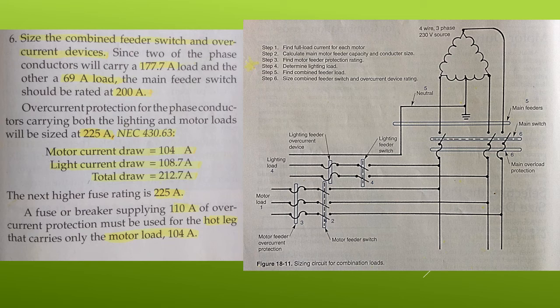The overcurrent protection for the phase conductors carrying both the lighting and the motor loads will be sized at 225 amps per NEC 430.63. We add the motor current draw, which is 104 amps, and the lighting current draw, which is 108.7 amps, which gives us a total of 212.7 amps, and the next higher fuse rating is 225 amps.